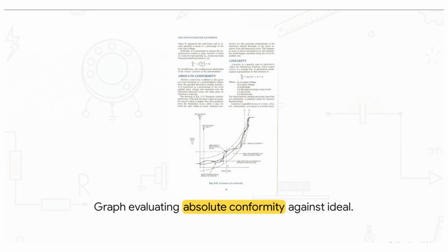When evaluating absolute conformity, you'll see how the actual electrical output, usually represented as a wavy solid line on these charts, can snake slightly above or below the theoretical straight dashed line. This happens because of microscopic manufacturing imperfections in the resistive track. And if you're designing a highly precise servo mechanism for aerospace, that little bit of snake in the output curve translates directly to physical positioning errors in your final product.